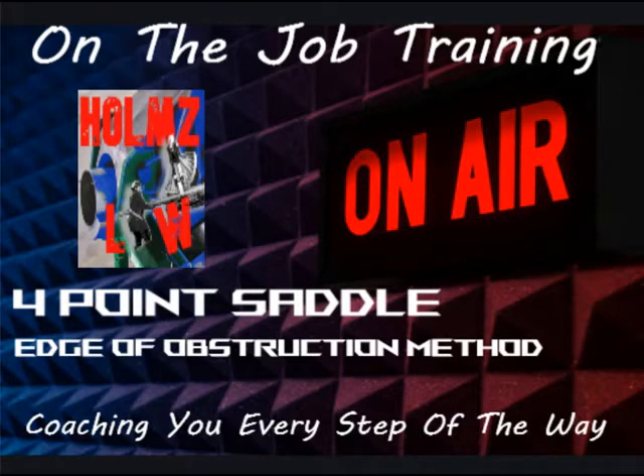Step 4, calculate the spacing between bends. Simply put, an example: if the height of your obstruction is 2 inches and you're bending 30-degree bends, the multiplier is 2. So that would be 2 times 2. Your spacing between bends value would be 4. I'm not going to speak about the multipliers because it's the same as the offset multipliers, and I'm pretty sure you can find that out anywhere else.